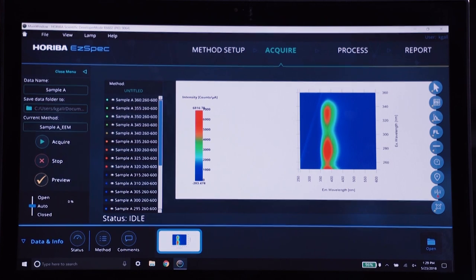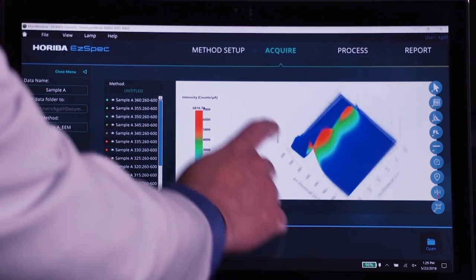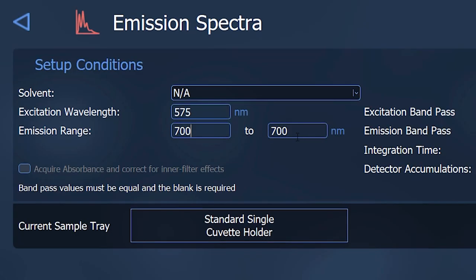And of course, if you're doing excitation emission matrices, we call them EEMs. We can now collect that entire EEM fingerprint in less than a minute, whereas before it might have taken an hour. But the other great benefit of the CCD is that it is able to detect further out into the near infrared, way beyond the wavelengths that are available with a traditional photomultiplier tube.